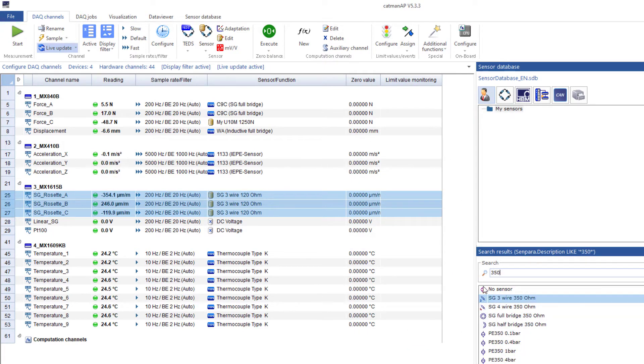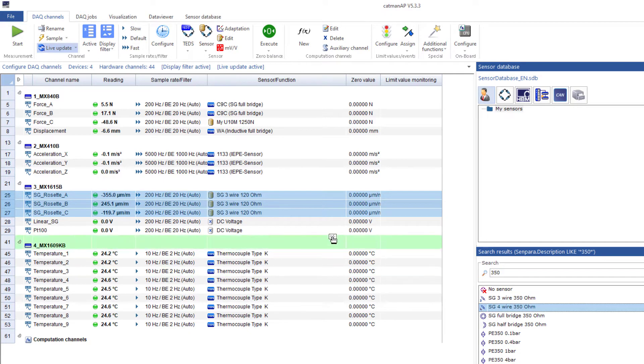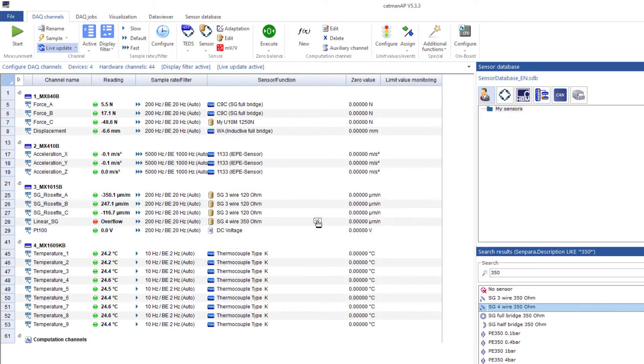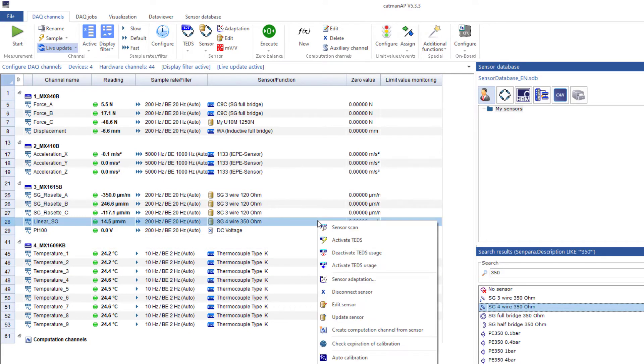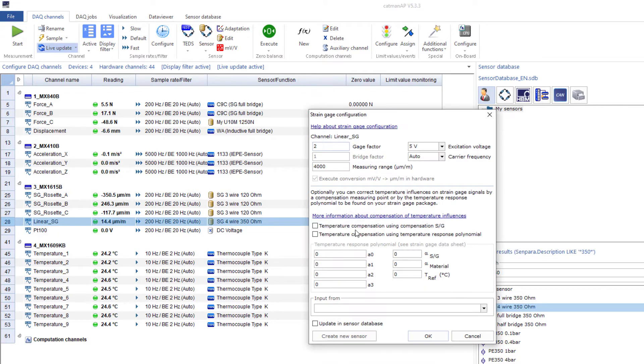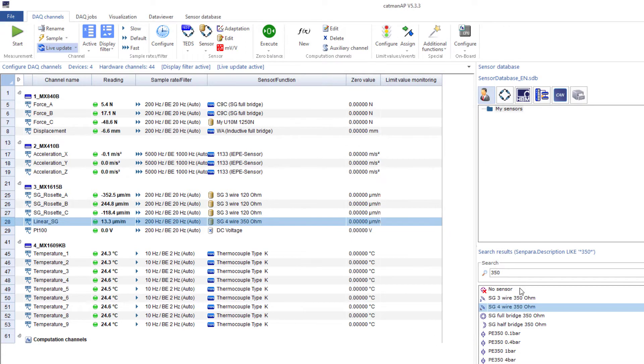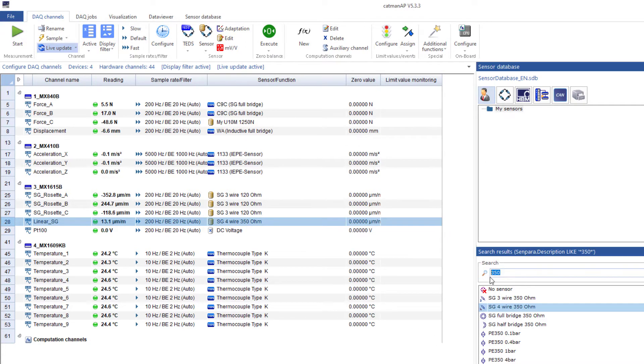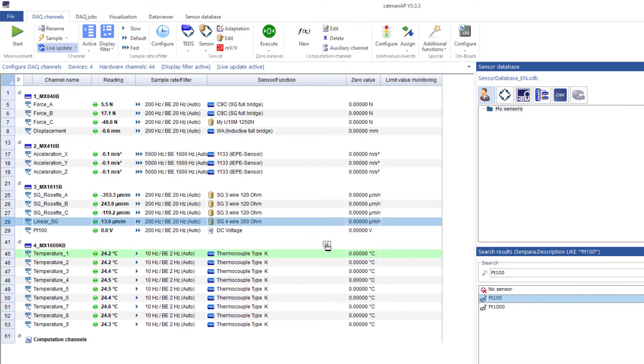The linear strain gauge has a four-wire circuit and 350 ohms. As you can see, I'll just use a matching search term to find the sensor. Now, I'll also store the gauge factor here. Finally, the PT100. Done!